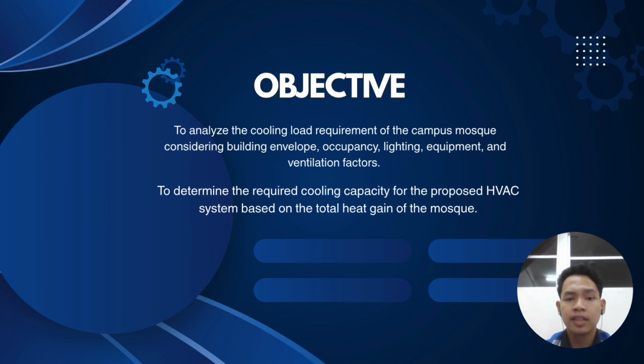First, to analyze the cooling load requirement of the campus mosques, thoroughly taking into account variables such as the building envelope material, occupancy number, electrical equipment, and required fresh air ventilation factor. Second, to determine the precise required cooling load capacity for the proposed HVAC system, measured in kilowatts or refrigeration tons, based on the calculated total peak heat gain of the mosque structures.